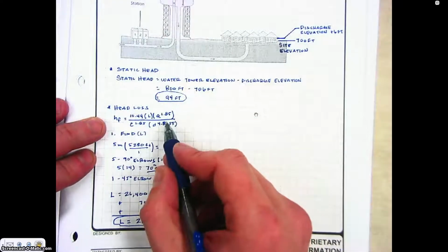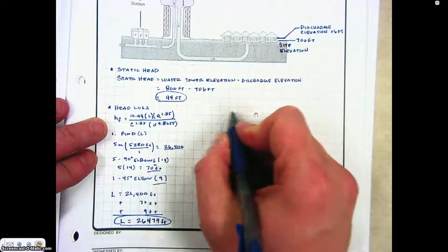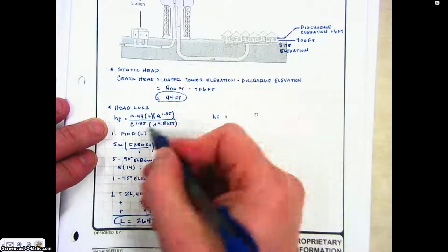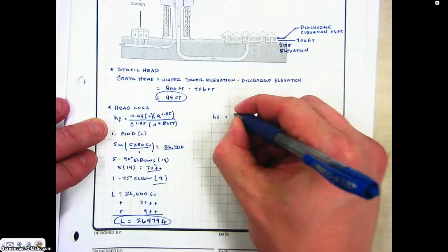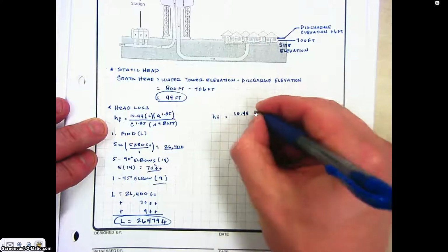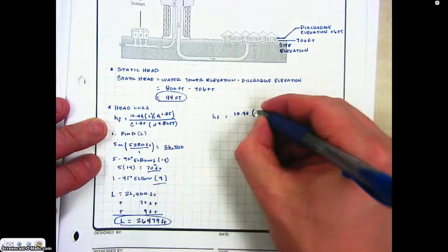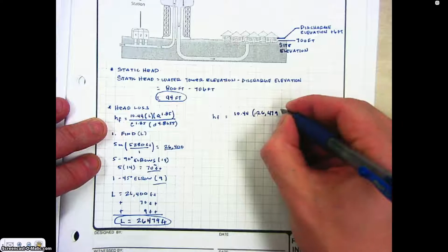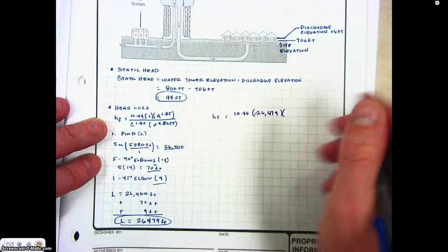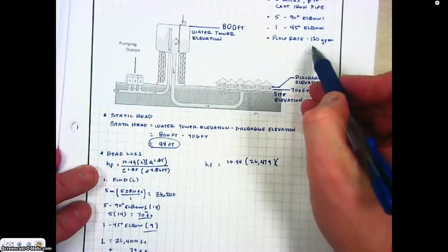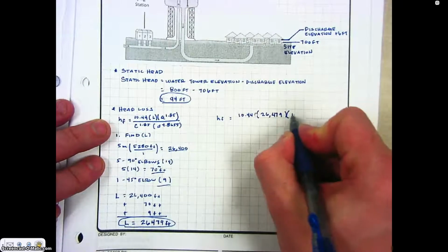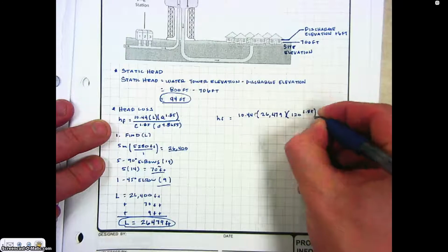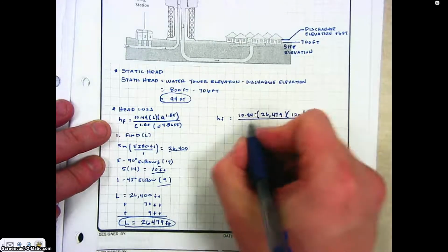And so that is the amount of feet we have in our system. Now we'll use the head loss formula, and I'll go ahead and write it over here. Head loss is equal to 10.44 times L, which we just solved for, 26,479, times the flow rate, which was 120 gallons per minute, and the flow rate is to the 1.85 power.